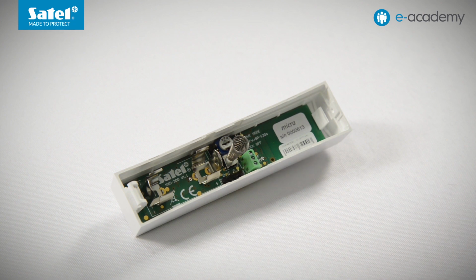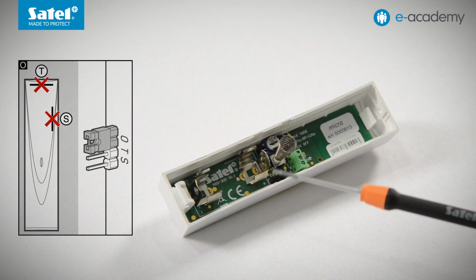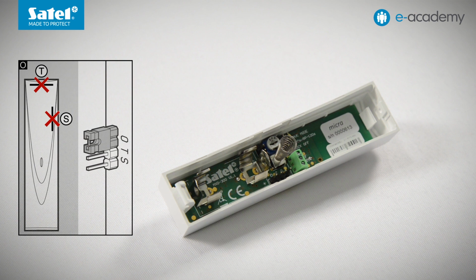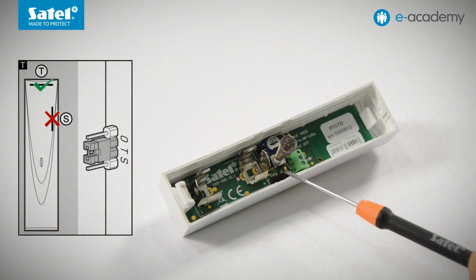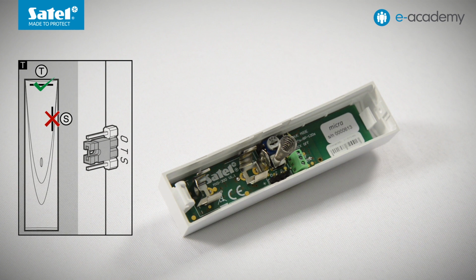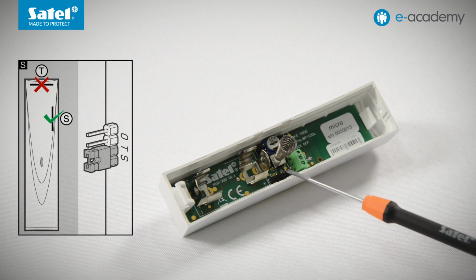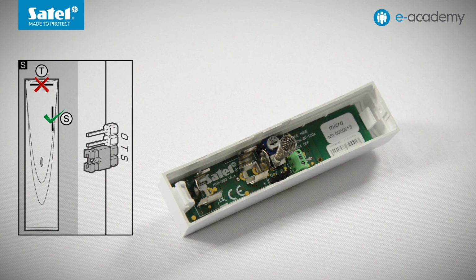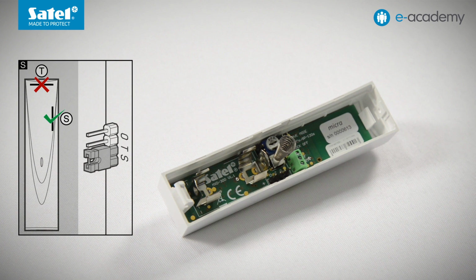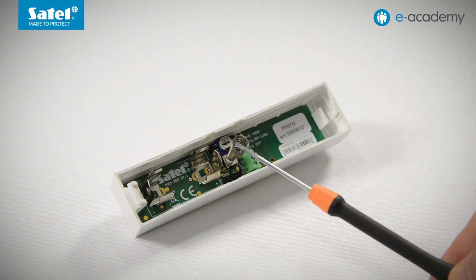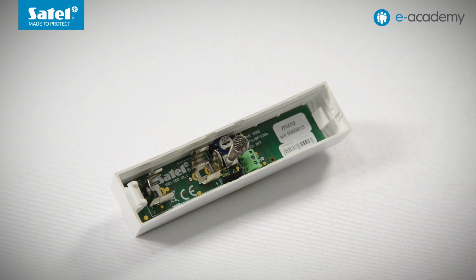They are used to configure the reed switches. If the pins next to the O marked are shorted, both reed switches are disabled. If the jumper is placed across the 2 middle pins, those next to the letter T, the reed switch located at the top edge of the detector will be enabled. T stands for top. And shorting the pins at the S mark, which stands for side, will turn on the side reed switch. In the middle of the electronics board, between the elements already discussed, there is a tamper contact, which responds to opening the enclosure or detaching the detector from the mount.